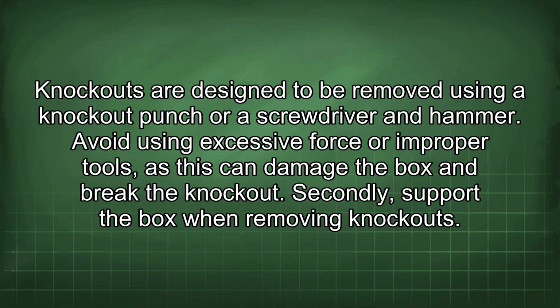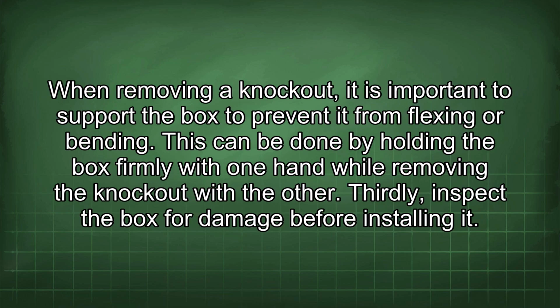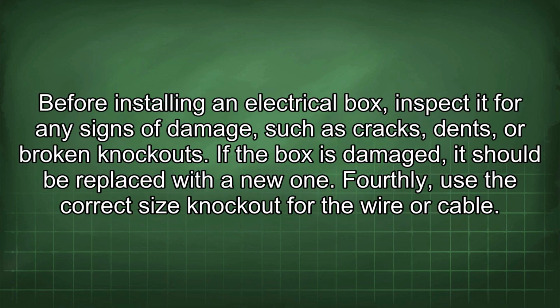Secondly, support the box when removing knockouts. When removing a knockout, it is important to support the box to prevent it from flexing or bending. This can be done by holding the box firmly with one hand while removing the knockout with the other. Thirdly, inspect the box for damage before installing it. Before installing an electrical box, inspect it for any signs of damage, such as cracks, dents, or broken knockouts. If the box is damaged, it should be replaced with a new one.